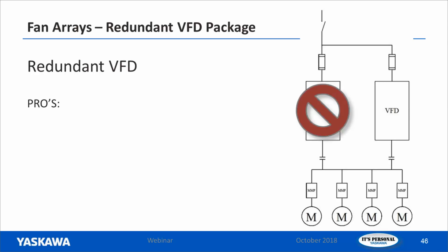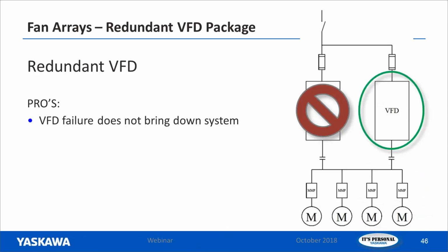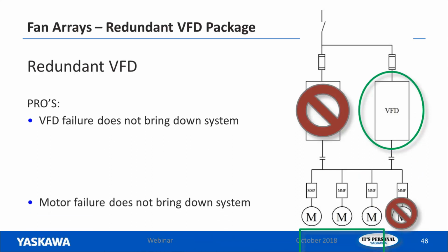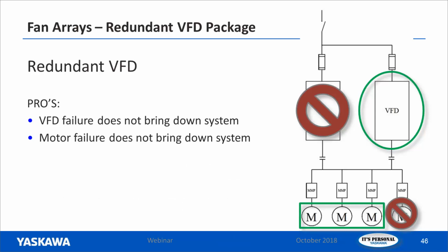So a pro would be, what happens if we lose a VFD or we get a fault? A VFD failure is not going to bring down the system. It's just going to switch to the other VFD. You're still going to be running your 4-motor array. Okay, what if we lose a motor in our array? Well, now we know that one motor failure is not going to bring the system down, and we can still run the remaining motors in the array, and the VFD can compensate however necessary to make sure we're still maintaining flow.